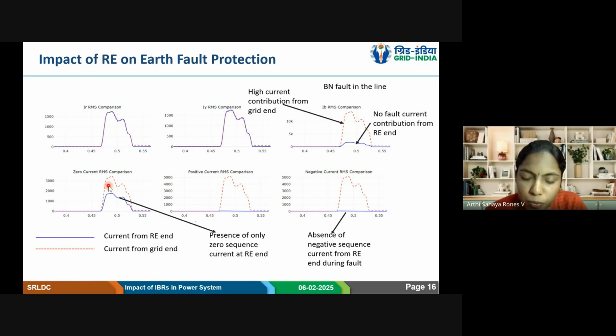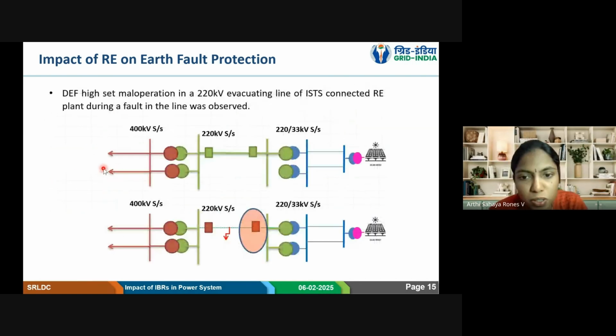So the factors that this zero sequence current depends on is the grounding of these interconnecting transformers. So we tried to simulate the same in PSCAD, and we were obtaining the same results. This kind of behavior not only comes when we have IBR, but also in a weaker system. When we are having radial loads connecting to the grid and where the system is very weak, that means it cannot contribute to the fault.